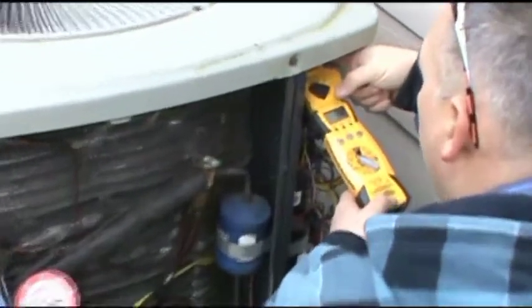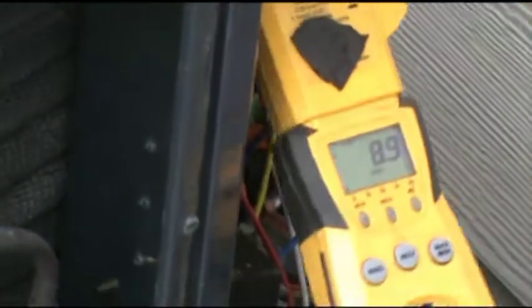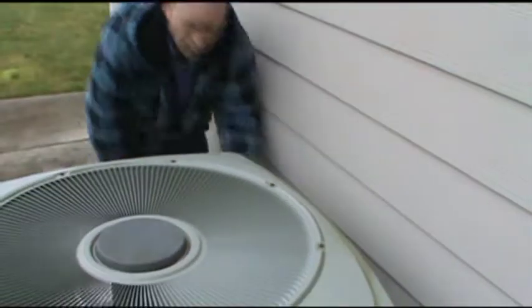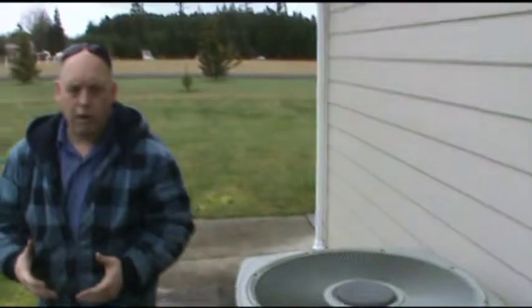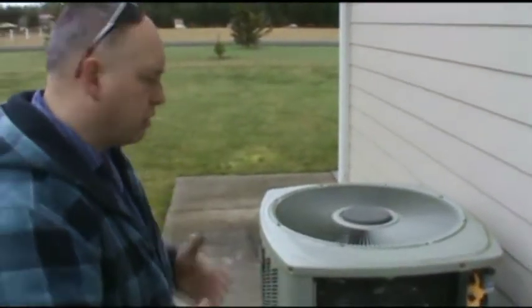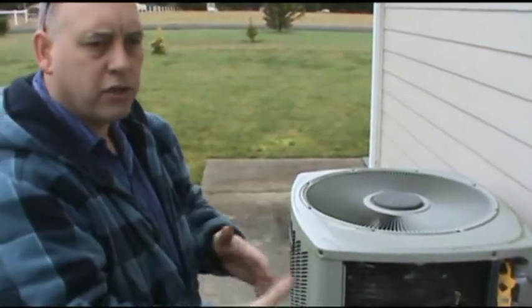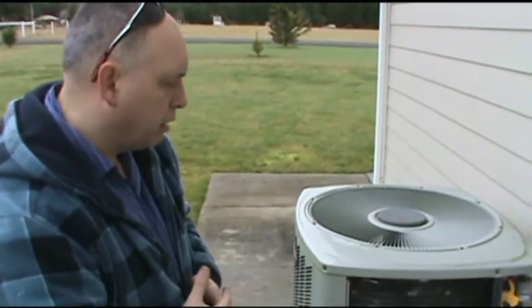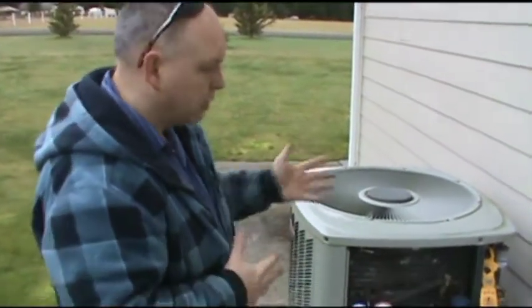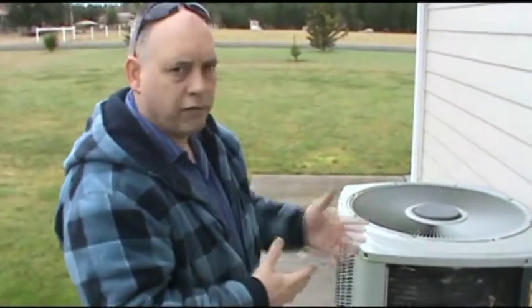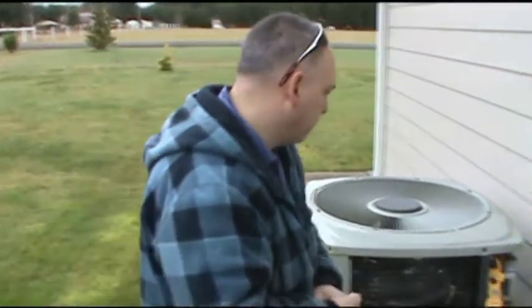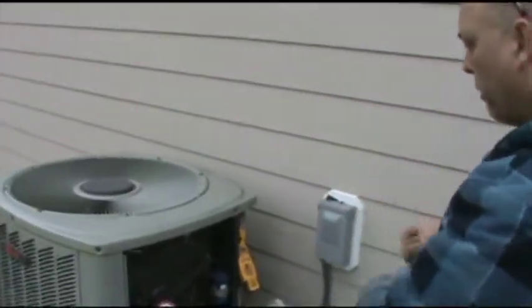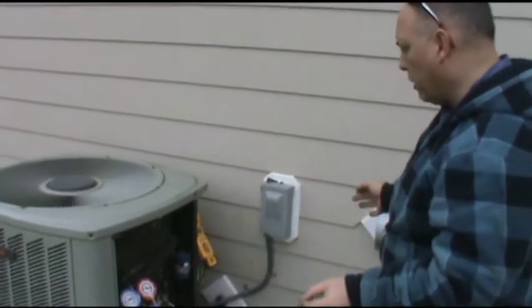We have compressor amps of 9.0. Our compressor is rated for 14.1. Under normal operating conditions, that should be around 65 to 75% of that rating, which is again right where we're at. 9 is roughly 65% of 14. So we've got good pressures, we've got good temperatures, we've got good amp draws. Everything is looking really good in here.